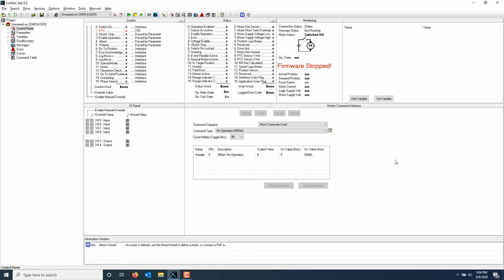Hello. In this video, we're going to discuss how to deal with a corrupt firmware installation on your LinMot drive. The firmware can become corrupted through an interrupted or incomplete firmware installation.